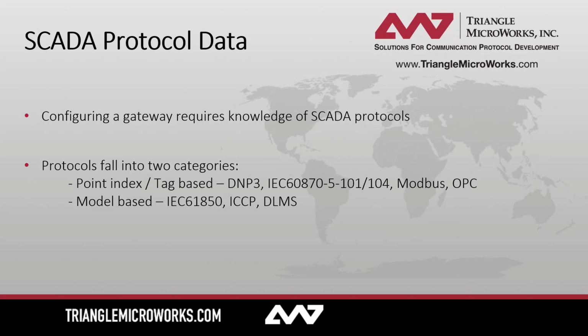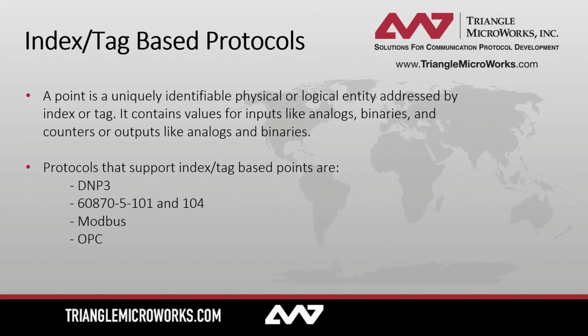So now let's talk a little bit about the data and its layout itself. Configuring a gateway does require knowledge of the SCADA protocols you'll be working with. Protocols can fall into two different categories: point index or tag-based protocols, or model-based. So index or tag-based protocols are set up like this: a point is a uniquely identifiable physical or logical entity addressed by an index or a tag. It contains a value for inputs like analogs, binaries, or counters, or outputs like analogs and binaries. Protocols that support index or tag-based points are DNP3, 60870-5-101 and 104, Modbus, and OPC.